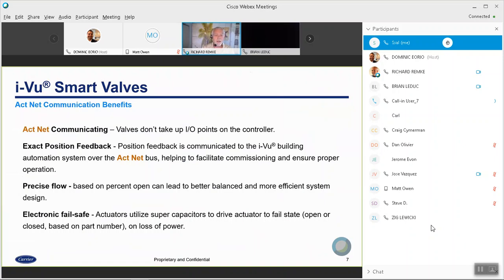So some of the benefits of using Act Net are that the valves don't take up any I/O points on the controller. You get exact position feedback. So when you're communicating with the valve, if you're telling it to go to 50%, you know that it's gone to 50%. You can get more precise flow based on the percent open, which can lead to better balancing of the system. And these actuators are based on the Belimo zone type valves, which have fail-safe actuator capabilities with supercapacitors built in, so you don't have to worry about any kind of spring. They can fail open or fail closed based on the part number, and we also have a fail-in-last-position option based on the part number.